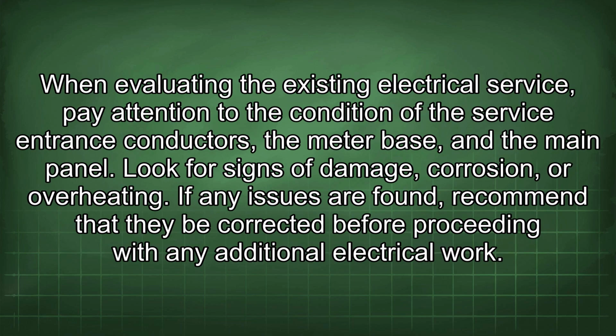When evaluating the existing electrical service, pay attention to the condition of the service entrance conductors, the meter base, and the main panel. Look for signs of damage, corrosion, or overheating. If any issues are found, recommend that they be corrected before proceeding with any additional electrical work.